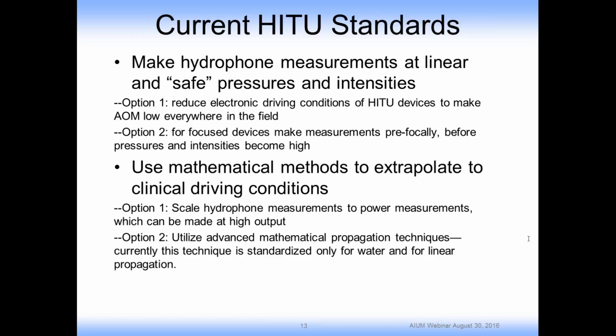Then what do you do? Well, that's the second bullet point. Some sort of mathematical extrapolation needs to be made to clinical driving conditions. In the case of that first option, where you made the hydrophone measurements at the low levels, well, you can scale to power measurements, which do not have these concerns, or at least not as much. It's much more feasible to make power measurements at the full output, and there is a procedure for scaling the hydrophone measurements at a low power output to the higher power output.